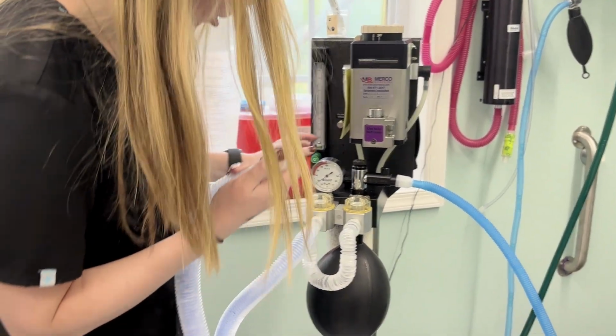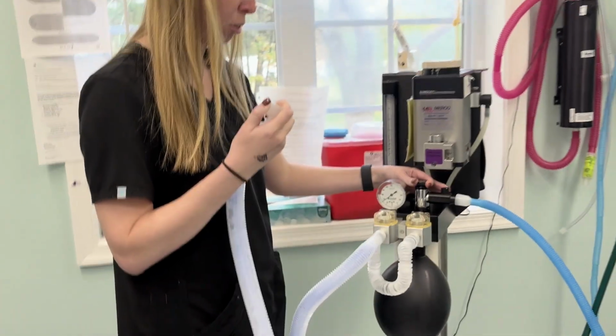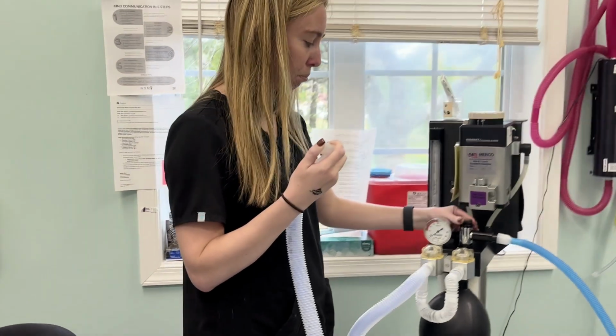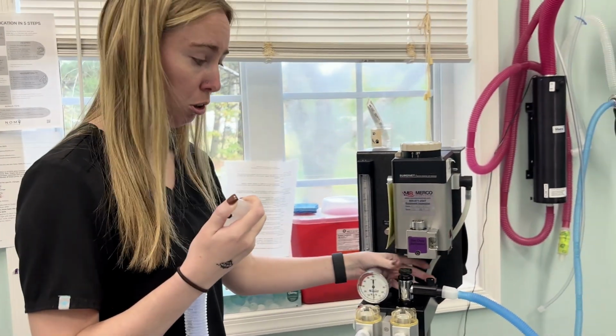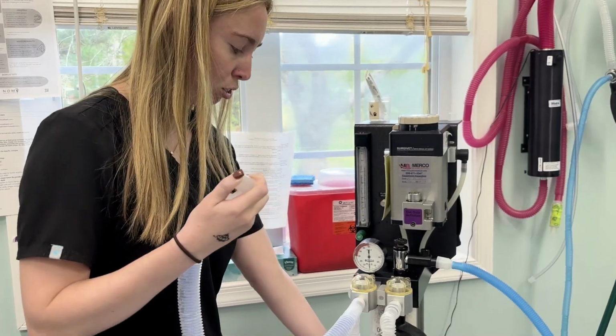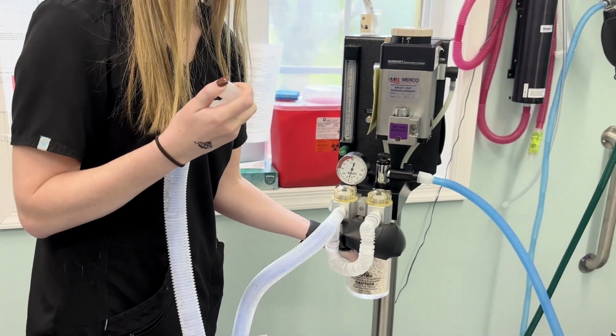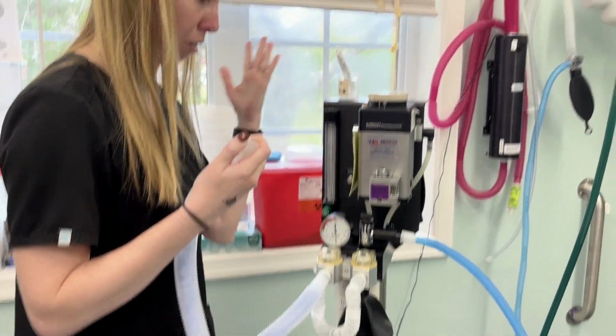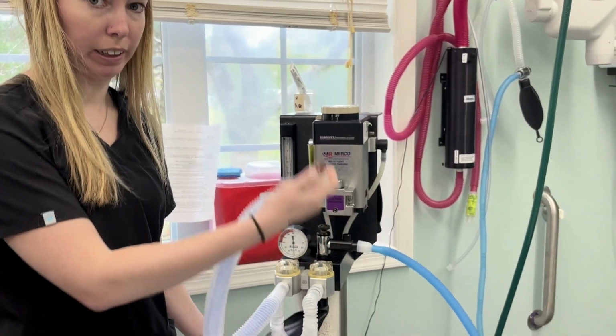And as long as that's doing good, then you can open up your pop-off valve again. You always want to make sure you open this up at the end. You can then squeeze the bag so that if there's any gases in the machine, it vents out of the pop-off valve, and then you can finally let your finger up. And that's how you check a machine.